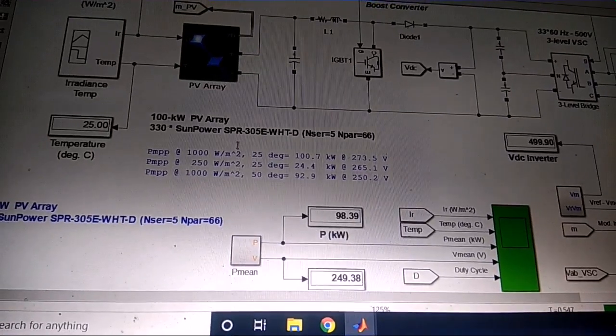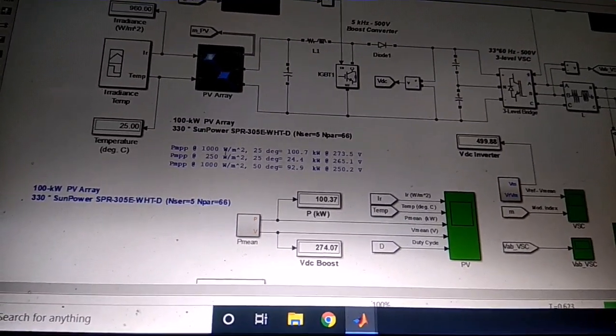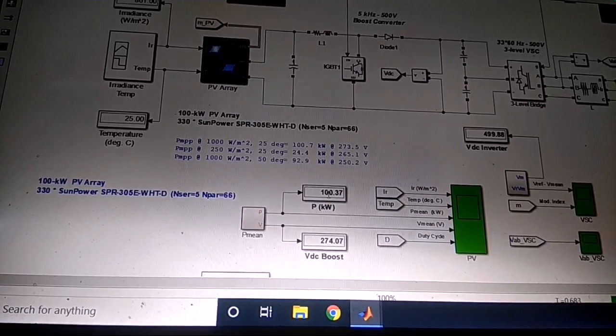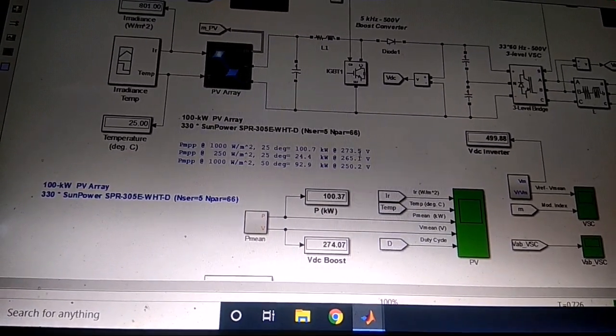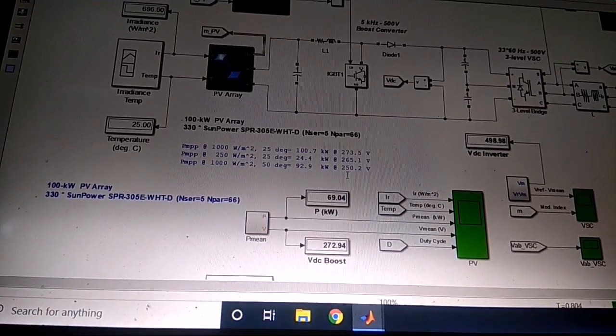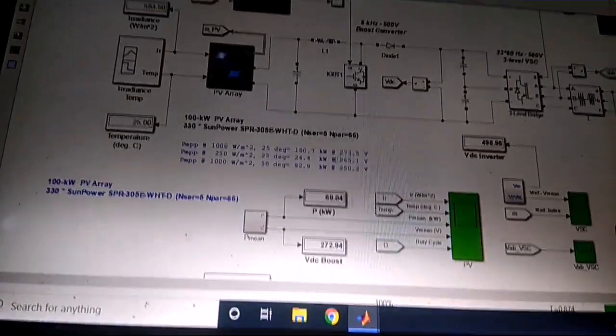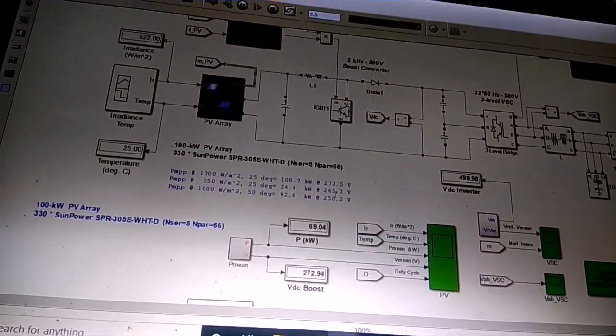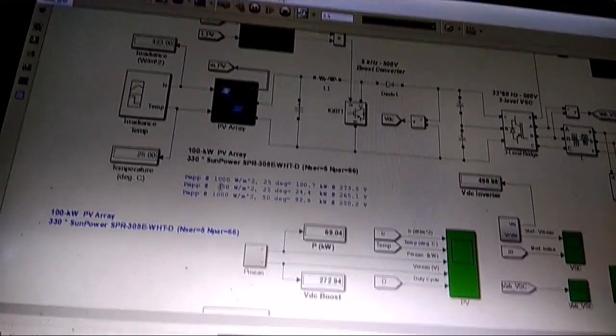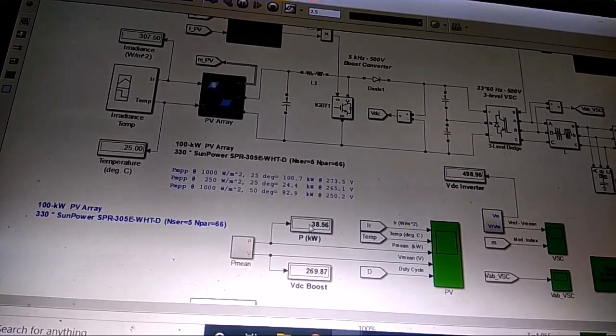When the radiation drops, you can see the power also drops. The initial maximum power is about 100 kilowatts. The boost converter DC voltage does not drop significantly — it only drops down to around 250 V — so you get a stable voltage level. The current level will change, but the voltage stays relatively stable. You can see the radiation has dropped to around 400 W/m² and the power is getting lower, which confirms the system is running correctly.